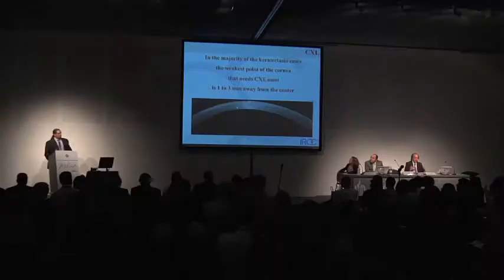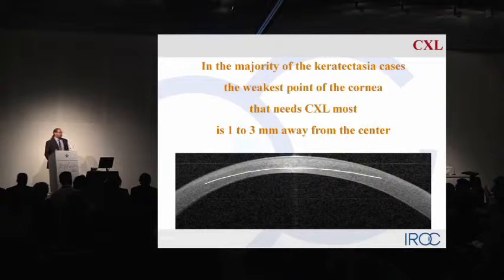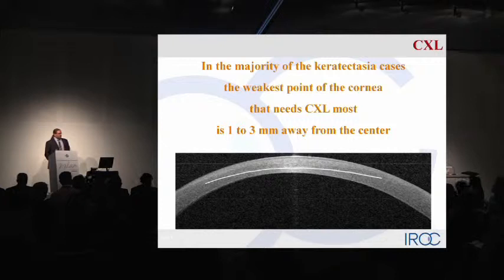Historically speaking, with cross-linking devices used in the past, we observed that the most effect is achieved more or less in the center of the apex, because that's where we center our treatment and that's where most of the illumination was applied. However, at the thinnest point, you can see at the demarcation line that the treatment area gets thinner. Over the thinnest point, we have practically no real effect. So the light application towards the specific cornea is of relevance. This is the demarcation line — as you can see, we're cross-linking maybe about 150 microns at the thinnest point, whereas in the center we have about 300 microns of cross-linking.